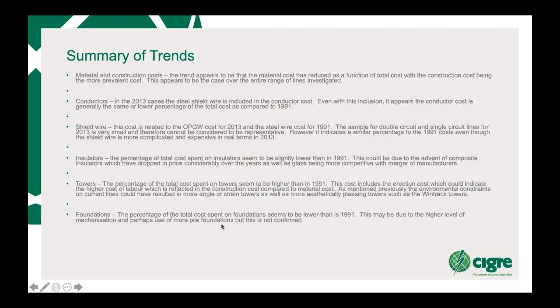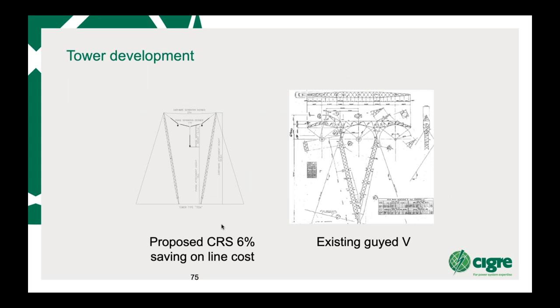So the big thing to remember is, if your total conductor cost is 10 to 15% of the total cost of the line, you've most probably got a reasonable line. Just looking here, and this is also compliments of Eskom, at different tower designs. This is with an existing guyed V, and this is the tower which I indicated with the negative shielding angle. This tower has problems relating to live line work because of the floating neutral point here. But as a configuration, it's actually quite a good tower from an electrical and mechanical point of view.